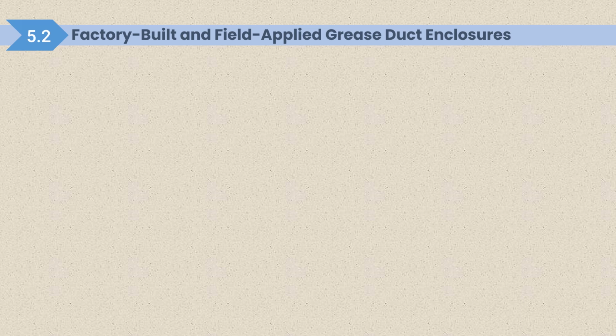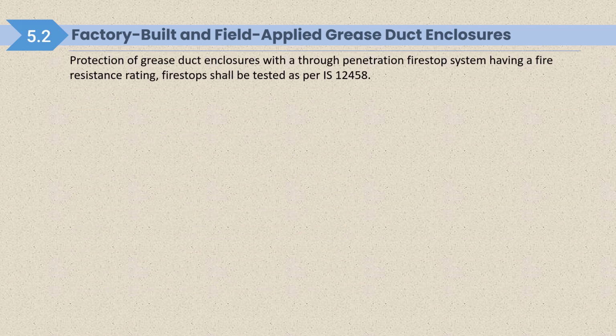In 5.2, factory built and field applied grease duct enclosures are mentioned. So we'll see the details. Protection of grease duct enclosures with a through penetration fire stop system having a fire resistance rating. Fire stops shall be tested as per IS 12458.